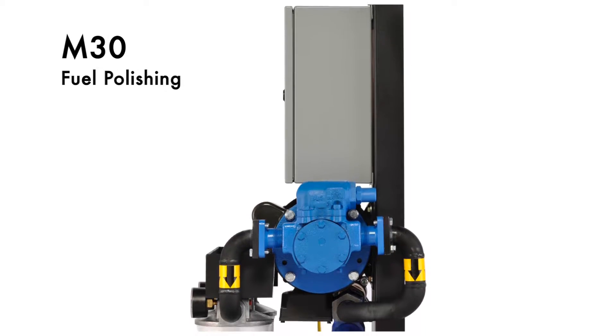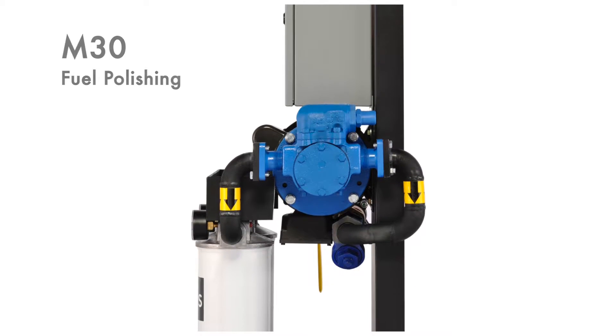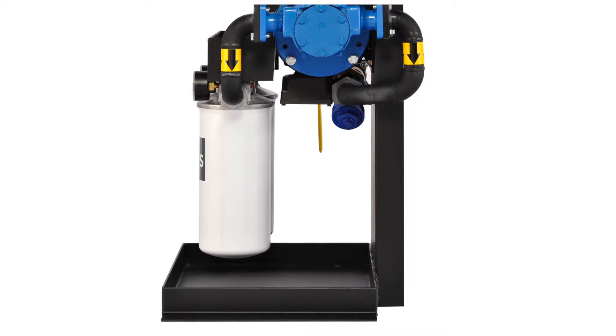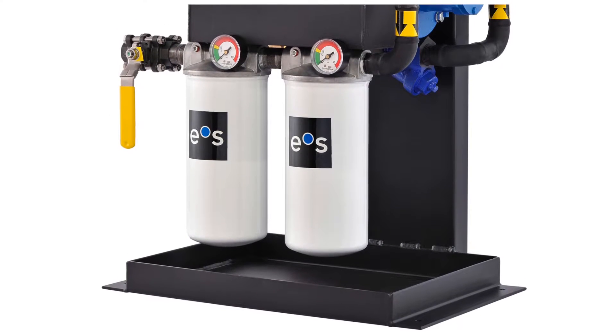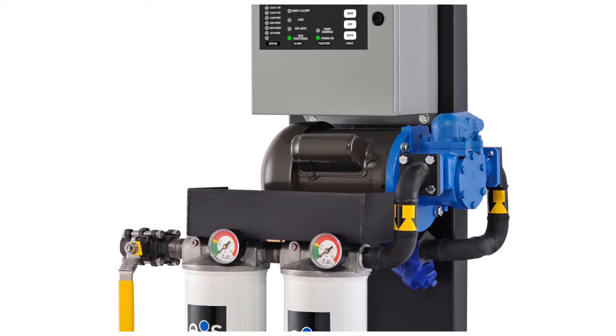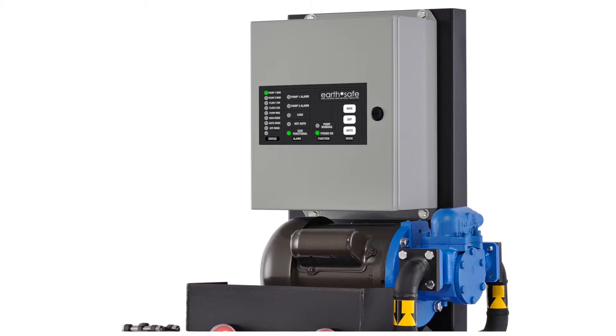The mechanical design is based on duty cycle pumps and filters, and is complete with strainers, check valves, ball valves, pressure gauges, and relief valves. The standard unit can handle up to 10 GPM with an option to add a motor starter for higher capacity needs.